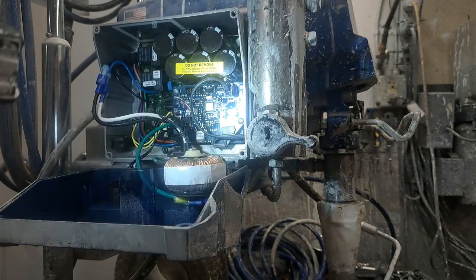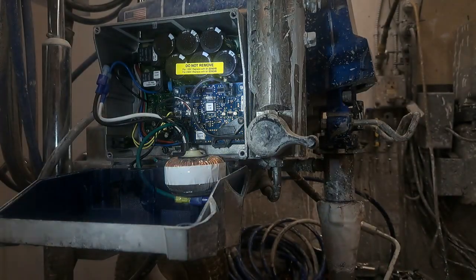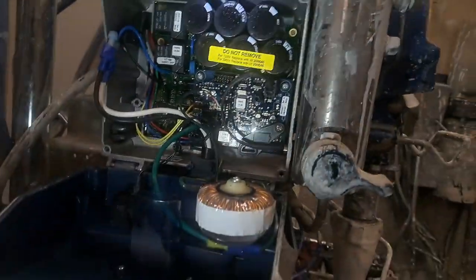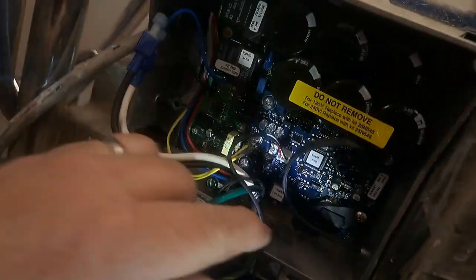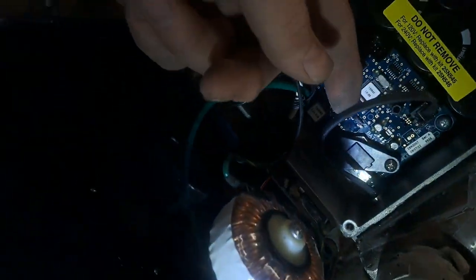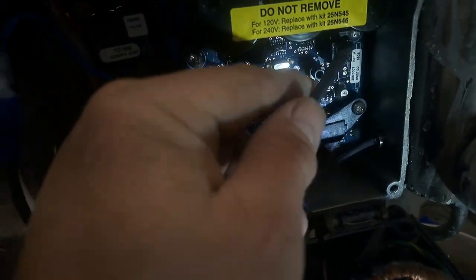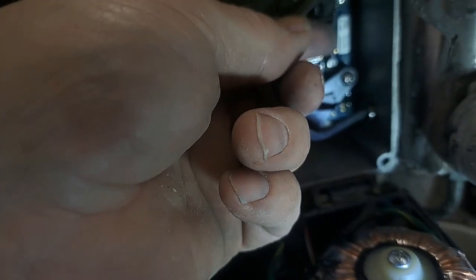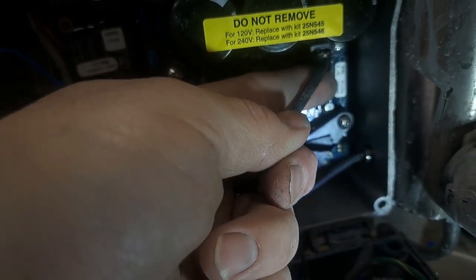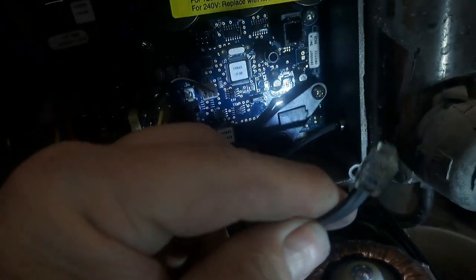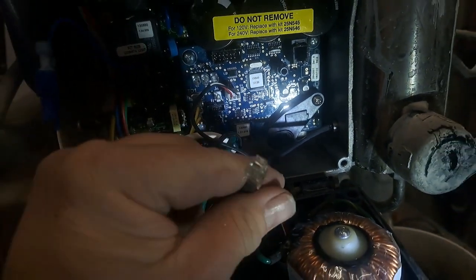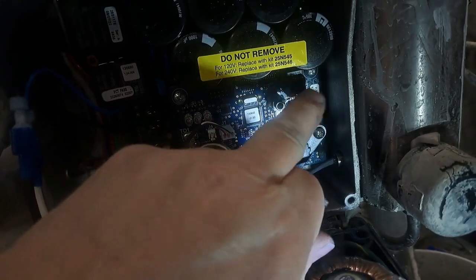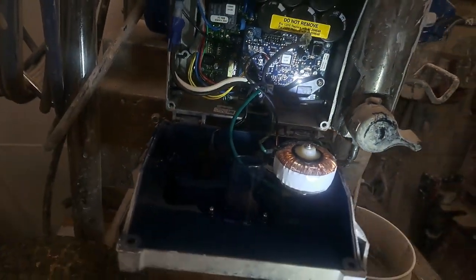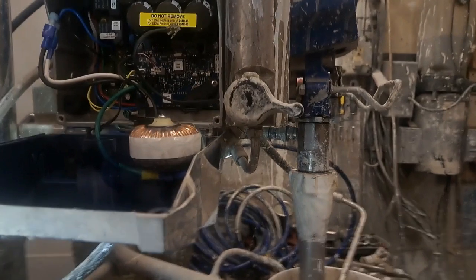It's aggravating. So we're going to turn the light on here. This black wire right here, let me get this out of the way so we can still use the light. That's your transducer wire, and it plugs in right there, just like the old style telephone cord. You lift up on the little tab and pull, and it comes out just like that, out of that black block right there. Be careful so you don't damage that block. So now the transducer itself is actually unplugged from the computer.